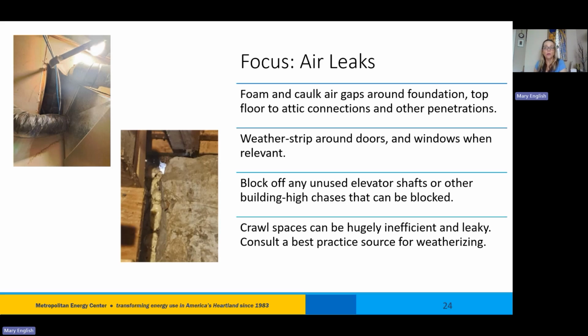Block off any unused elevator shafts or other building height chases that can be blocked. I was just in doing an energy assessment a couple weeks ago where there was an old elevator shaft that had lots of leaks. Those shafts just act like a furnace flue - especially in the winter, the hot air just goes like a freight train out through that shaft.